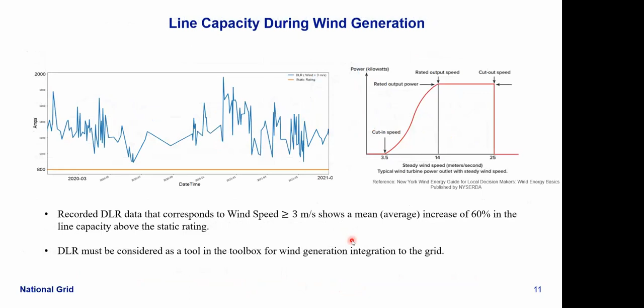Dynamic power flow control is another device that we've installed on our transmission system. As I mentioned in my intro earlier, these devices are connected to our EMS. So through our energy management system, I can send a command signal to reduce the power flow on line X, because the loading is getting close to the static rating or the dynamic rating, whatever the reason. I can send that signal and say, push the power away from that line, or pull more power through that line. That way I can manage the congestion on my transmission system.